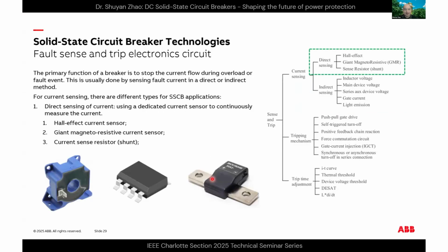Okay, just finish. Okay. So the next is the fault sensing and trip electronics circuit. The primary function of a breaker, of course, is to stop the current flow during overload or fault events. So this is usually done by sensing fault current in a direct or indirect way. For current sensing, there are different types for solid state circuit breaker applications. Direct sensing of current uses a dedicated current sensor to continuously measure the current, like a Hall effect current sensor, giant magnetoresistive current sensor, or a current sense resistor or shunt resistor current sensor.